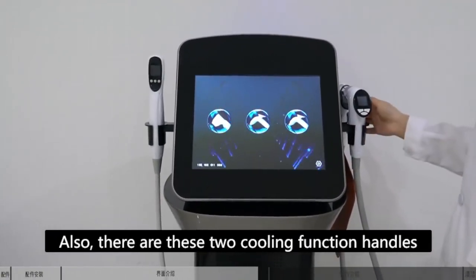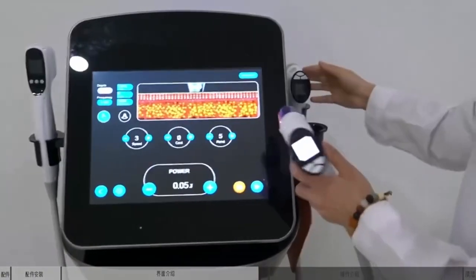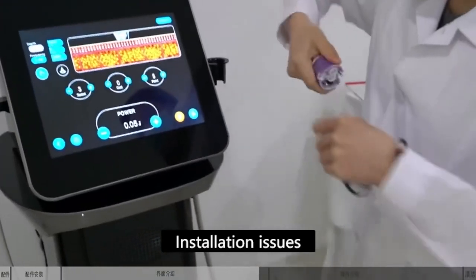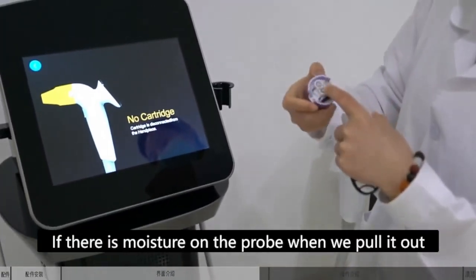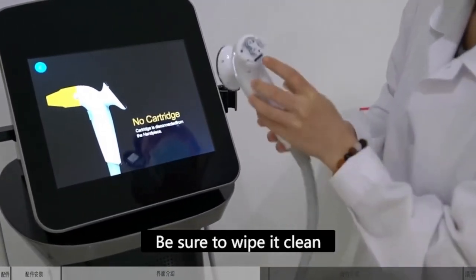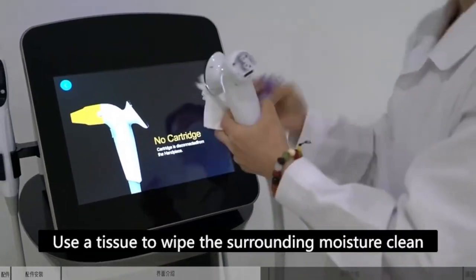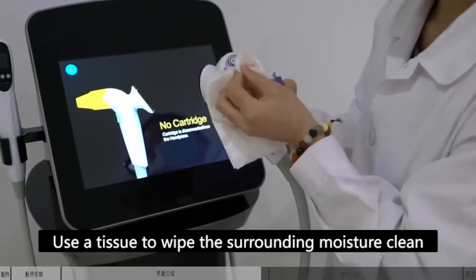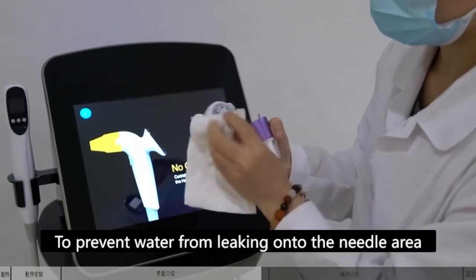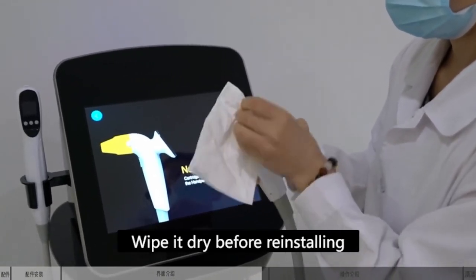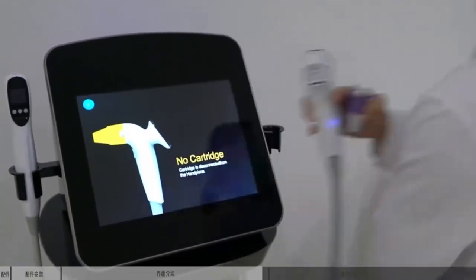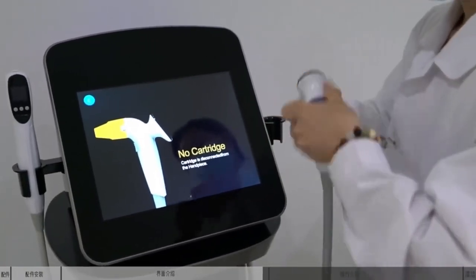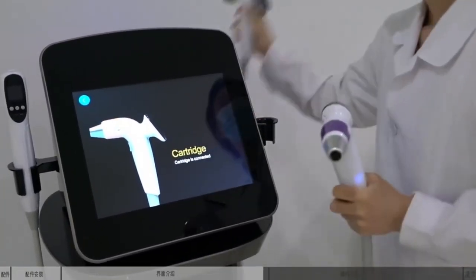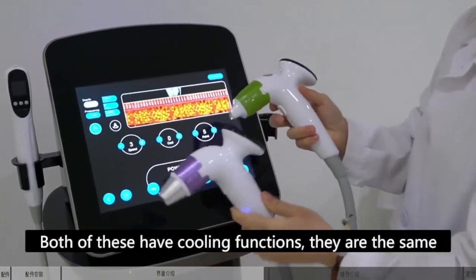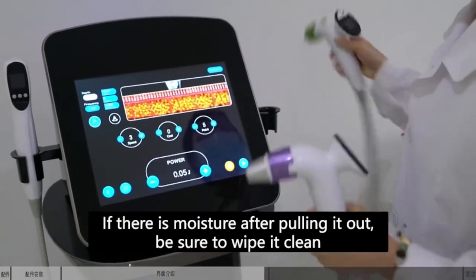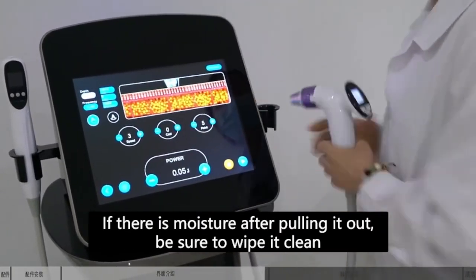Also, there are these 2 cooling function handles. Installation issues. If there is moisture on the probe when we pull it out, be sure to wipe it clean. Use a tissue to wipe the surrounding moisture clean to prevent water from leaking onto the needle area. Wipe it dry before reinstalling. Both of these have cooling functions, they are the same. If there is moisture after pulling it out, be sure to wipe it clean.